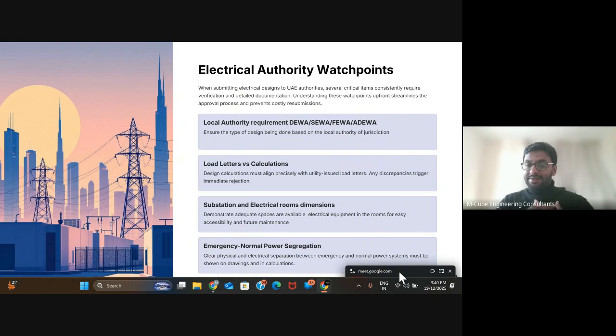Another important point for electrical design is proper segregation of emergency power. Here you see the interrelationship between different standards - electrical requirements as well as civil defense requirements. Civil defense specifies staircase pressurization, corridor pressurization, smoke fans, and extract fans, all of which need to be on emergency power. As electrical engineers, you need to ensure these requirements from other authorities are integrated into your design, collaborating with the HVAC design engineer to make sure essential powers are properly integrated.